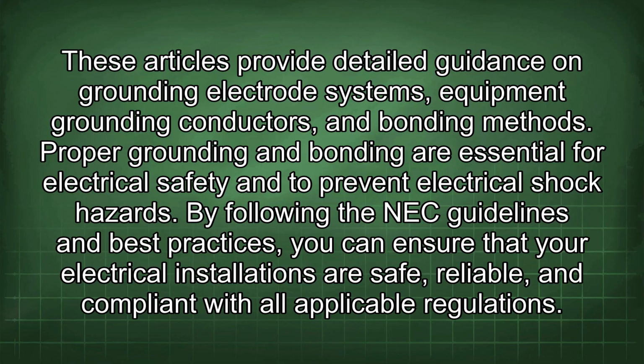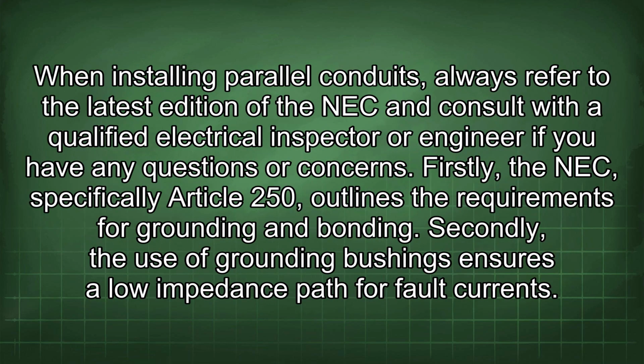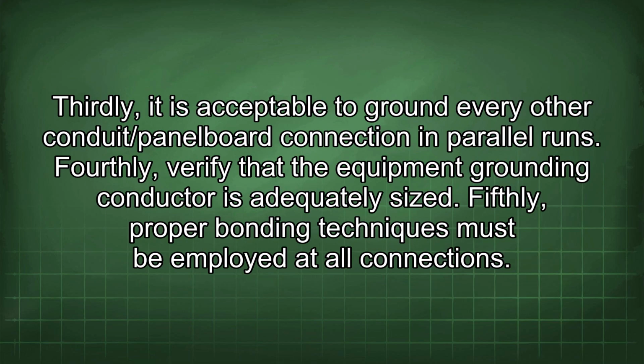By following the NEC guidelines and best practices, you can ensure that your electrical installations are safe, reliable, and compliant with all applicable regulations. When installing parallel conduits, always refer to the latest edition of the NEC and consult with a qualified electrical inspector or engineer if you have any questions or concerns. Firstly, the NEC, specifically Article 250, outlines the requirements for grounding and bonding. Secondly, the use of grounding bushings ensures a low impedance path for fault currents. Thirdly, it is acceptable to ground every other conduit/panel board connection in parallel runs.